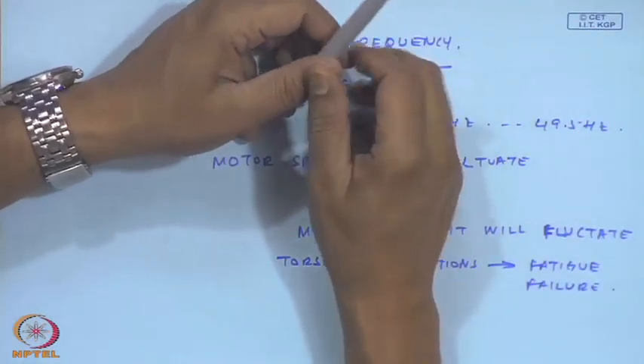If I put in more steam, there have to be governors to limit it so that it will run at 50 hertz. Otherwise, if I do not govern it, the speed will increase and the power supply frequency is going to increase. We all take it for granted, but a generator is supposed to run at a constant speed. If I give in more fuel or more steam to a steam generator, it is going to speed up. You would have noticed that in IC engines: if you press the throttle more, your car moves faster because the engine is moving faster. But imagine if your generator moved faster, your supply frequency is going to change. So these are things we cannot take for granted.